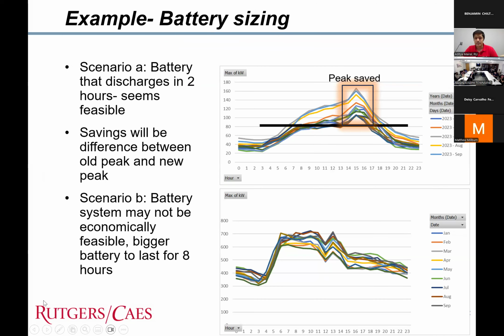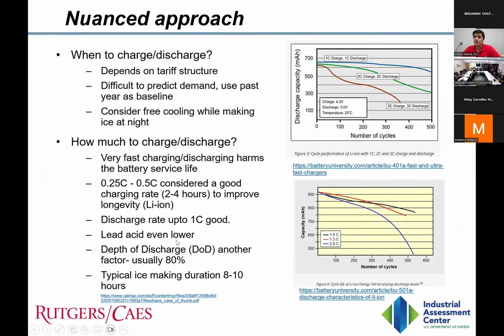If they have a load profile that's constant throughout the day and don't have enough time to charge the batteries, then the economics become difficult. What I'm trying to say is these rules help you size the batteries, discharging over 2 to 4 hours. If there's a peak for just 15 minutes, a very small peak, we still want the battery to discharge over 1 hour for the capacity it has. It can still provide 15 minutes to reduce the peak, and the rest would just be to reduce usage and use it back. But this 2 to 4 hours is important.